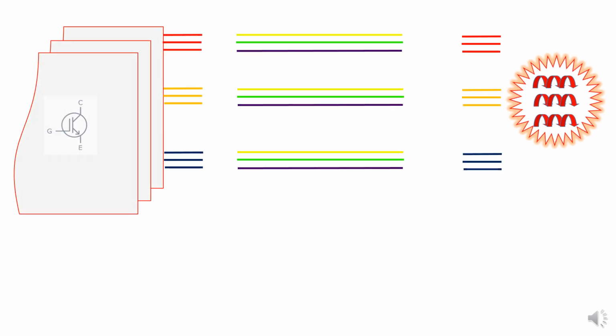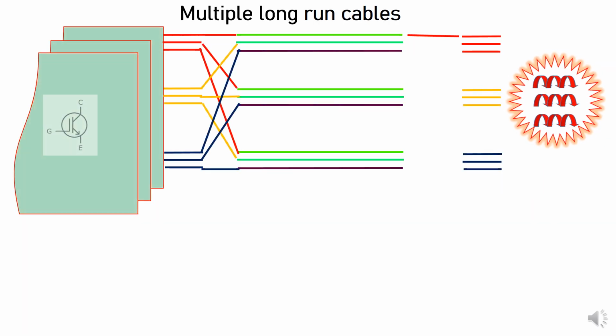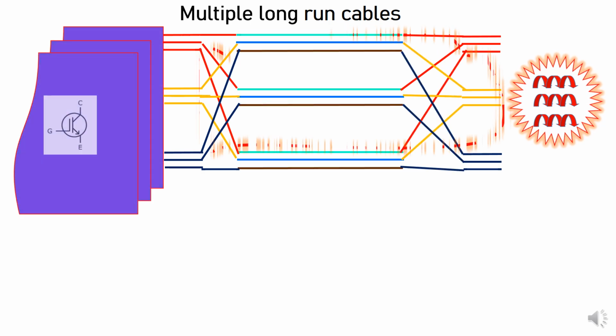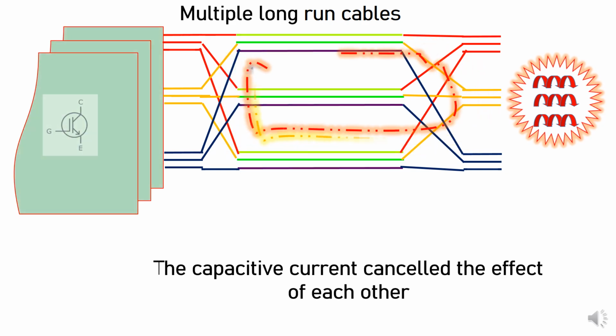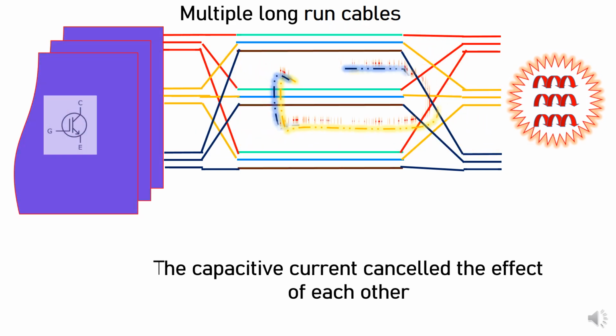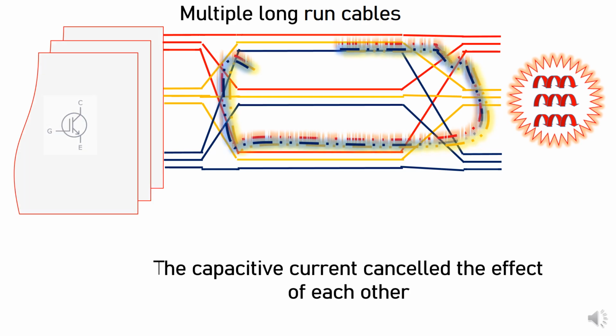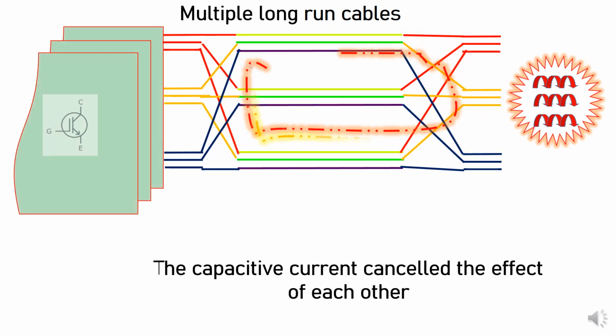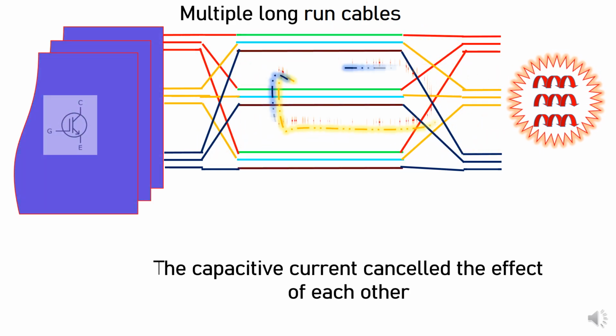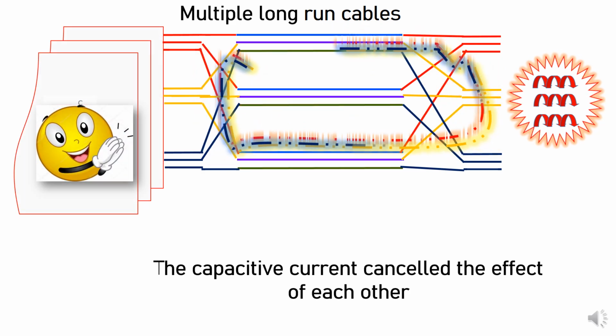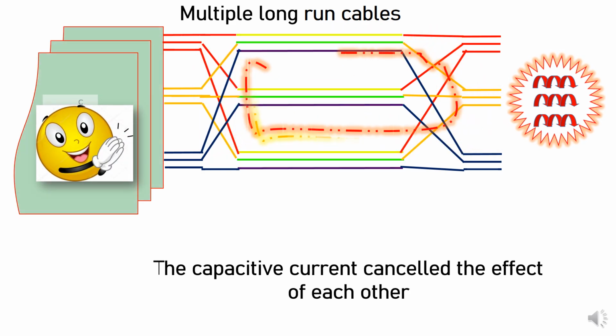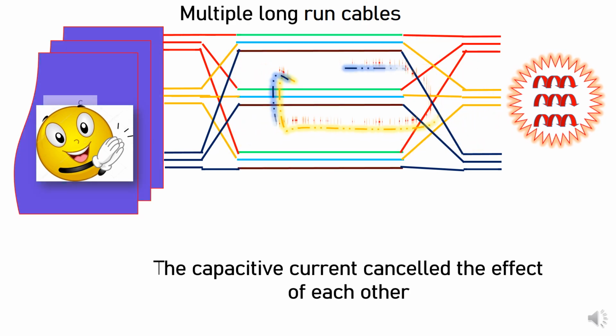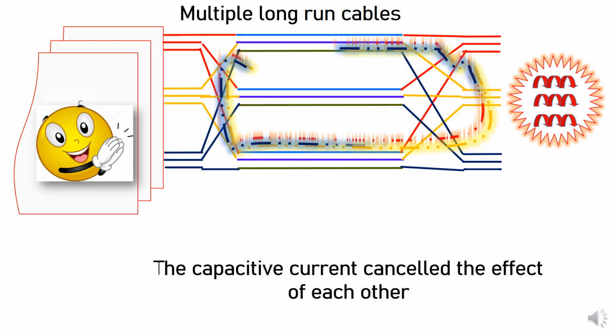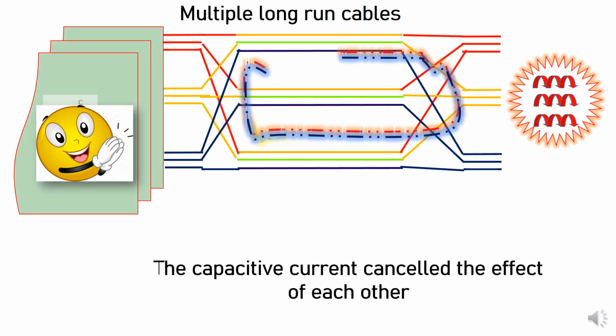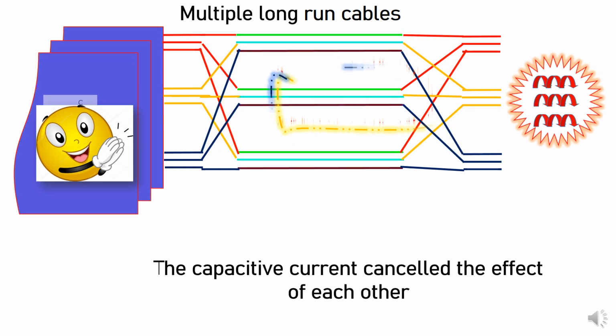The same advantage you can see here in what we have discussed about the capacitive type of current. With such type of arrangement, the capacitive current also will nullify each other, and at last your capacitive current remains near the minimum value, and you will never face VSD overcurrent fault. So these are the two biggest advantages of doing the connection at the VSD end and at the motor end, what I have mentioned. That is called a transposition of the cable, and you will get a fantastic result, so that you can avoid the capacitive current and at last the overcurrent fault by the VSD.